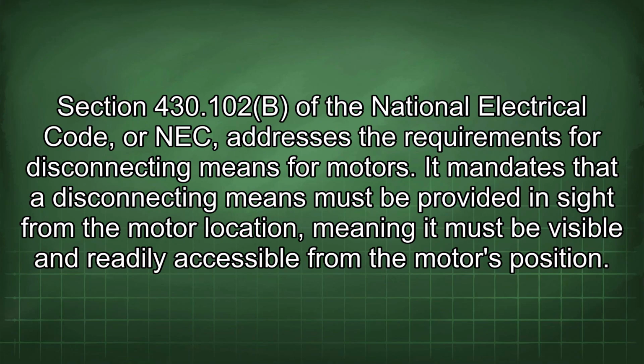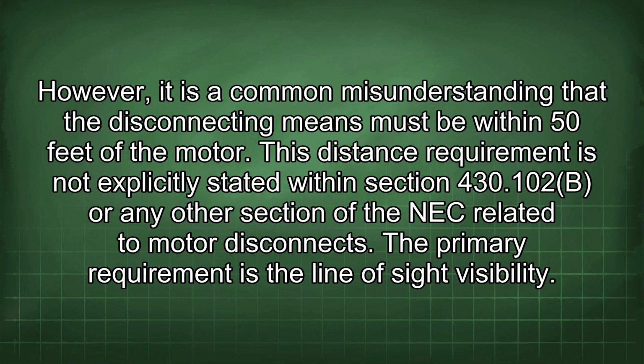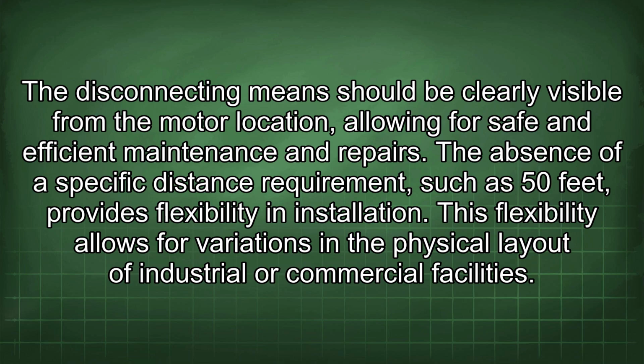430.102b of the National Electrical Code, or NEC, addresses the requirements for disconnecting means for motors. It mandates that a disconnecting means must be provided in sight from the motor location, meaning it must be visible and readily accessible from the motor's position. However, it is a common misunderstanding that the disconnecting means must be within 50 feet of the motor. This distance requirement is not explicitly stated within Section 430.102b or any other section of the NEC related to motor disconnects. The primary requirement is the line of sight visibility. The disconnecting means should be clearly visible from the motor location, allowing for safe and efficient maintenance and repairs.